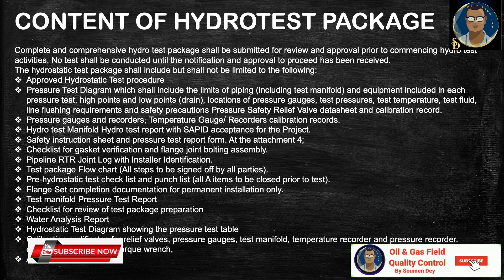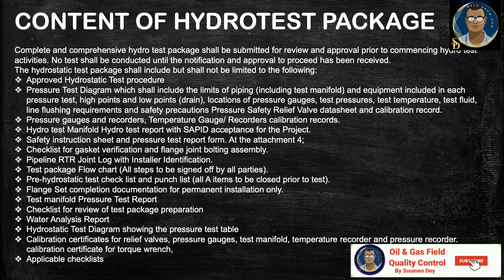A comprehensive hydrotest package shall be submitted for review and approval prior to commencing hydrotest activities. No test shall be conducted until the notification and approval to proceed has been received. The hydrostatic test package shall include but not be limited to: approved hydrostatic test procedure, pressure test diagram including limits of piping, test manifold and equipment, high points and low points drain, location of pressure gauges, test pressure, test temperature, test fluid, line flushing requirements, safety precautions, and pressure safety relief valve data sheet and calibration record.